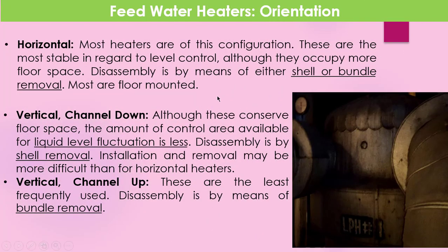As per orientation, the feed water heaters are horizontal and vertical. The horizontal heaters are most stable in regard to level control, although they occupy more floor space. Disassembly is by means of either shell or bundle removal, and most are floor mounted.